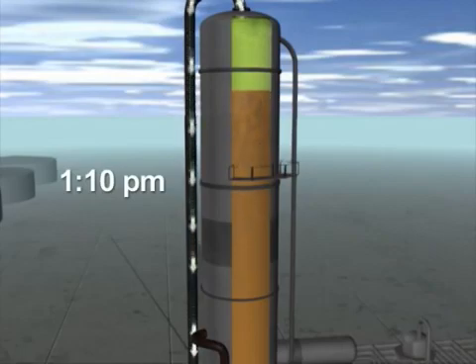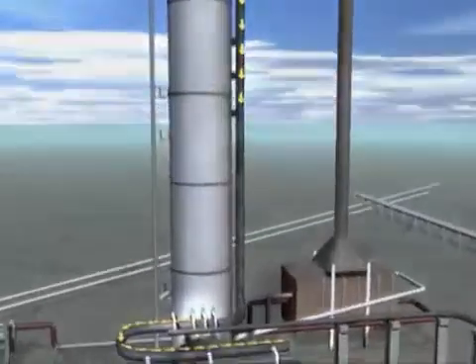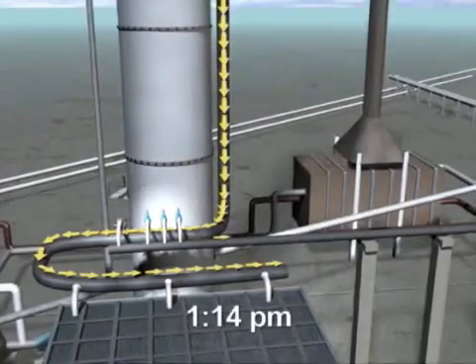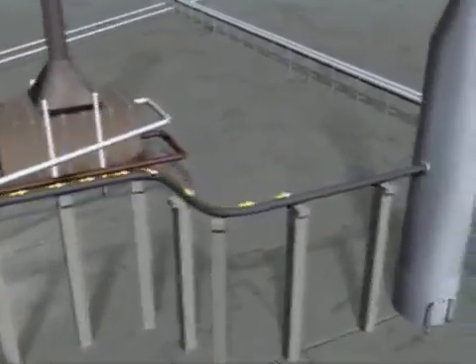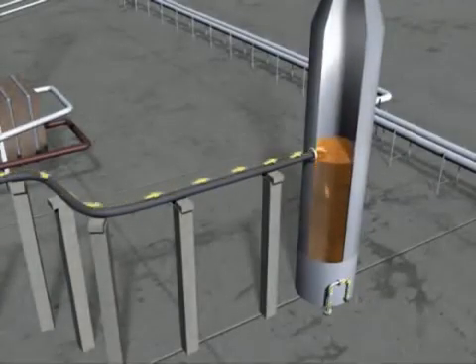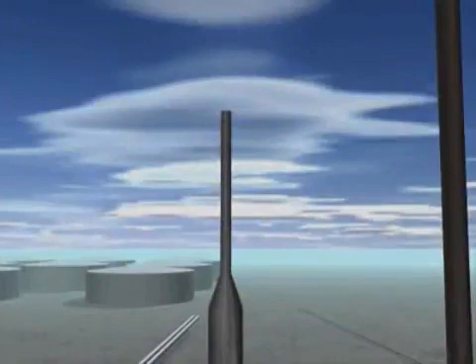At 1:10 p.m., the tower began overflowing liquid into the piping off the top of the tower. Liquid built up in this vertical piping and exerted great pressure on the emergency relief valves 150 feet below. At 1:14 p.m., the three emergency valves opened and liquid began flooding the blow-down drum at the other end of the isomerization unit. Some liquid overflowed from the blow-down drum into a process sewer, but the high-level alarm on the blow-down drum didn't go off.